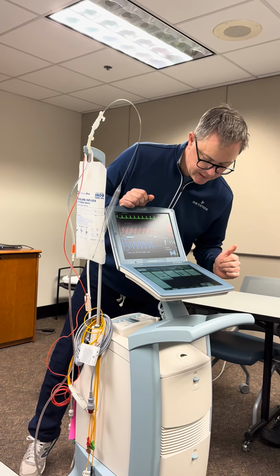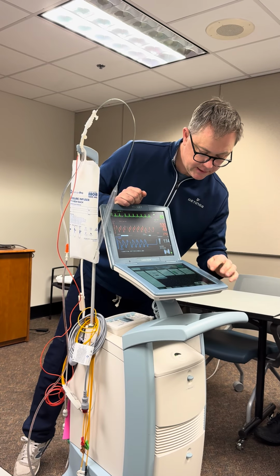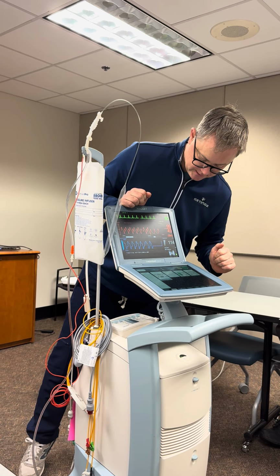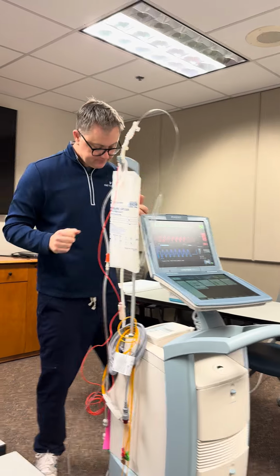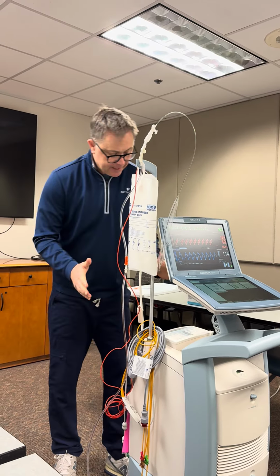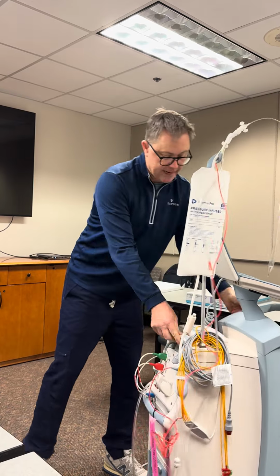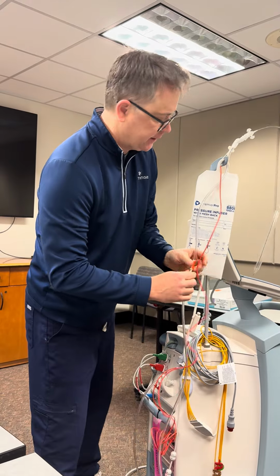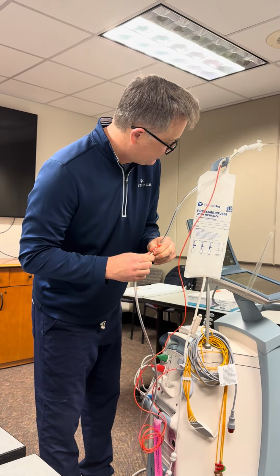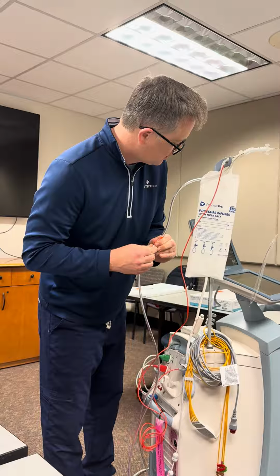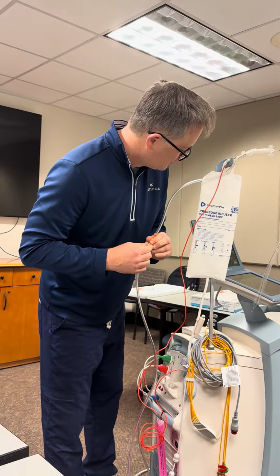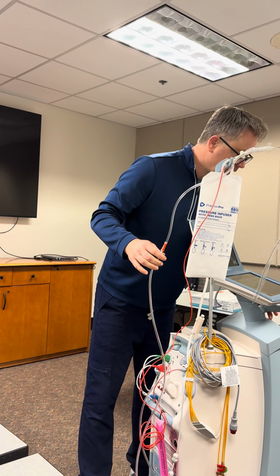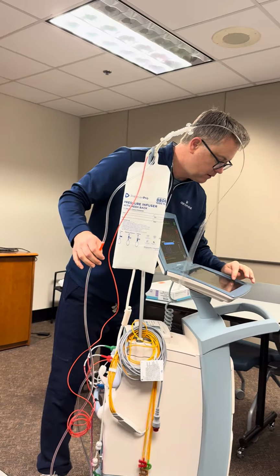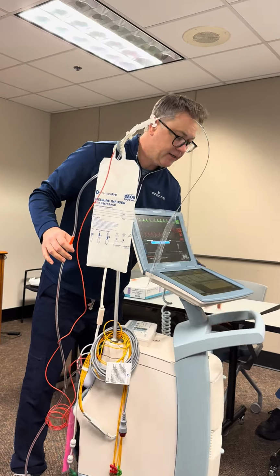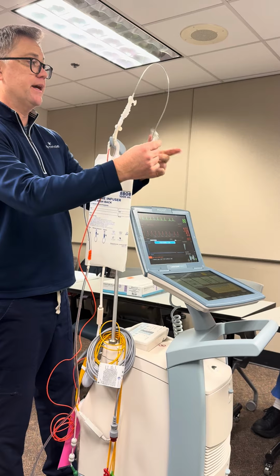Some of the common alarms you'll see, let's see. Any kind of gas loss, gas gain, so we'll see if we can replicate that. Any gas loss, gas gain alarms. A gas loss in the circuit alarm should trigger your brain that possibly the balloon catheter is ruptured.